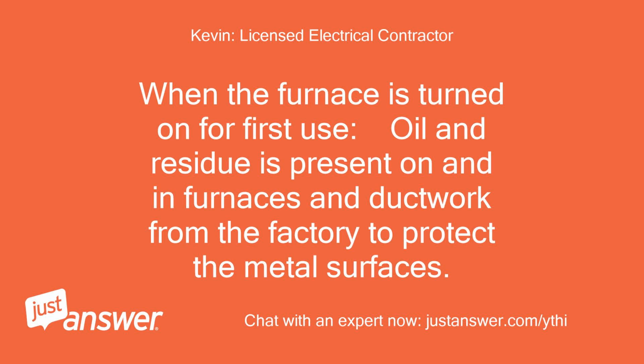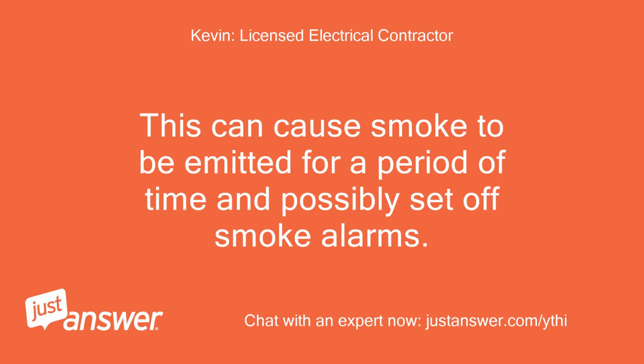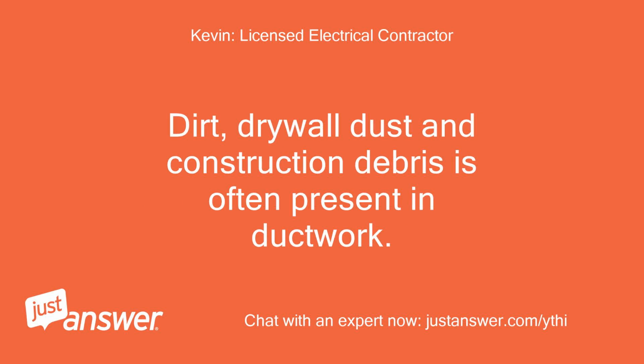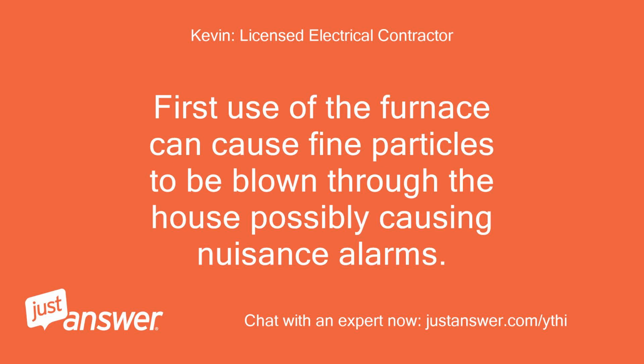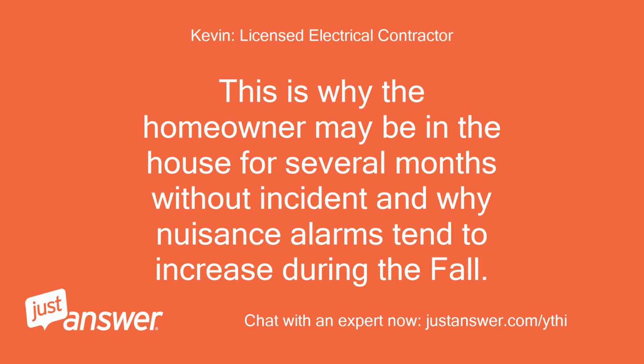When the furnace is turned on for first use, oil and residue is present on and in furnaces and ductwork from the factory to protect the metal surfaces. This can cause smoke to be emitted for a period of time and possibly set off smoke alarms. Dirt, drywall dust and construction debris is often present in ductwork. First use of the furnace can cause fine particles to be blown through the house, possibly causing nuisance alarms. This is why the homeowner may be in the house for several months without incident and why nuisance alarms tend to increase during the fall.